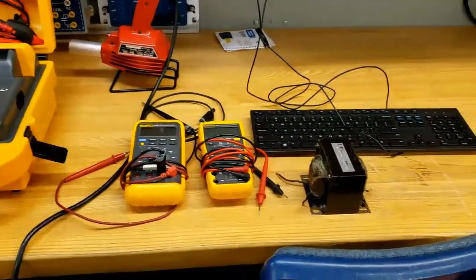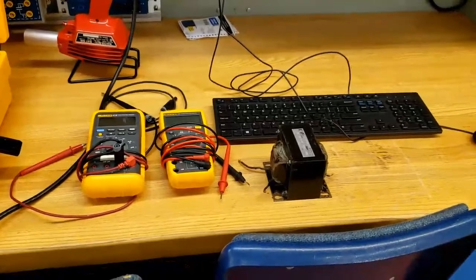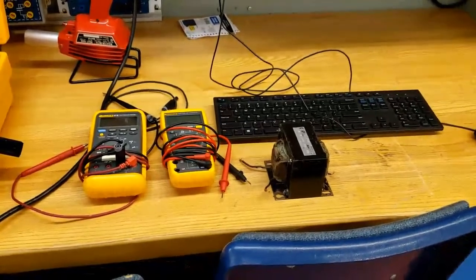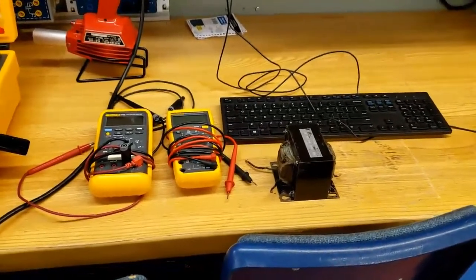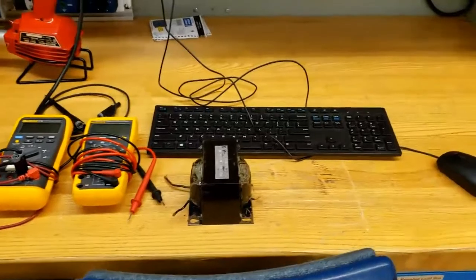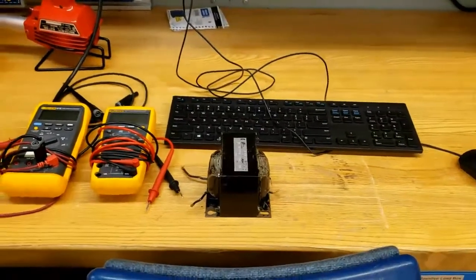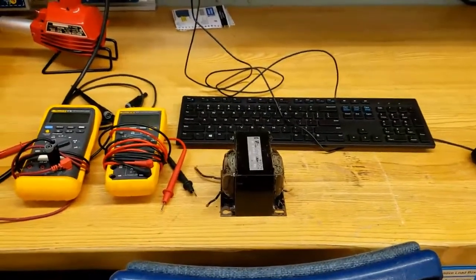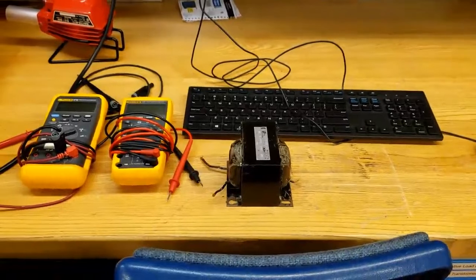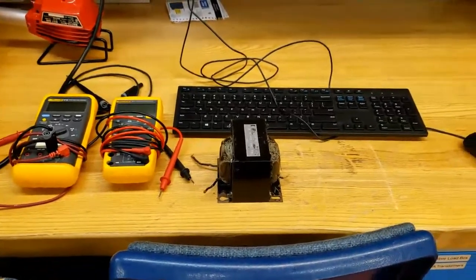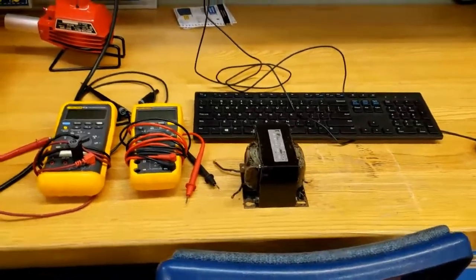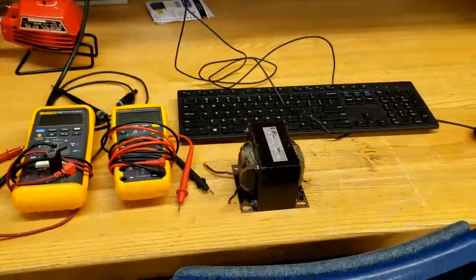And check your current. If your current is in the high 100 nano or microamps at the start, it will drop quickly once you start heating it. Once the current gets down to 1 or less than 1 microamp, you're pretty much done. You may do the second 10-minute test, but you may not need to at this point. That will get you started.